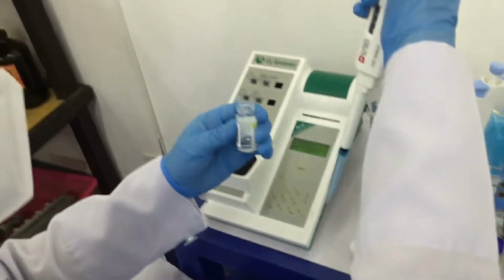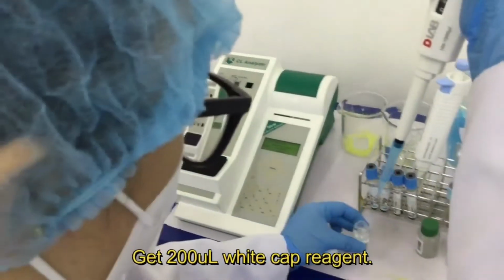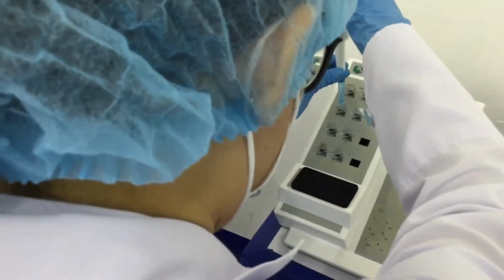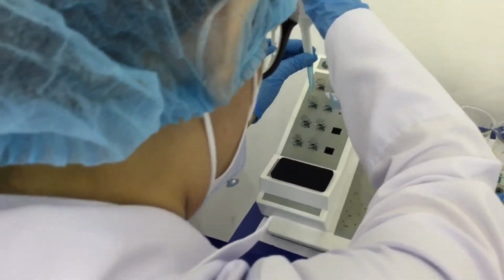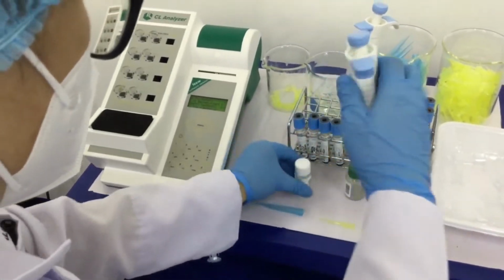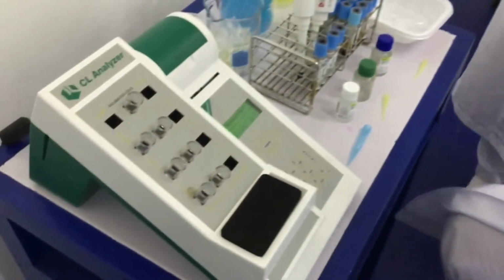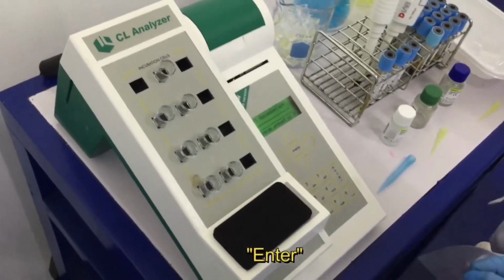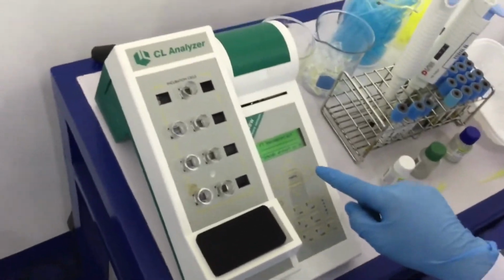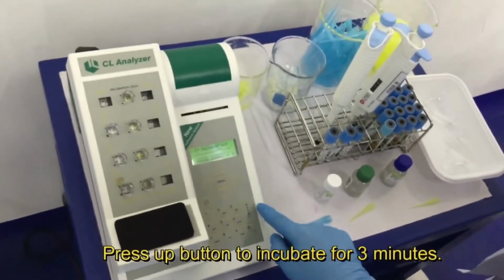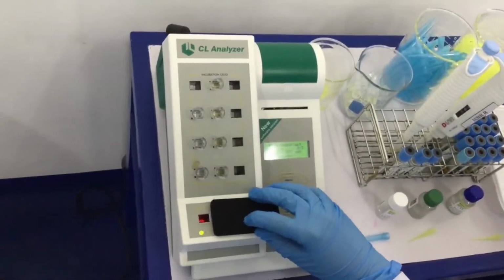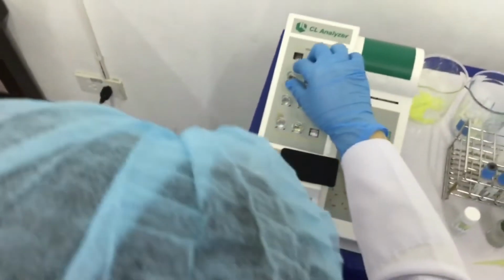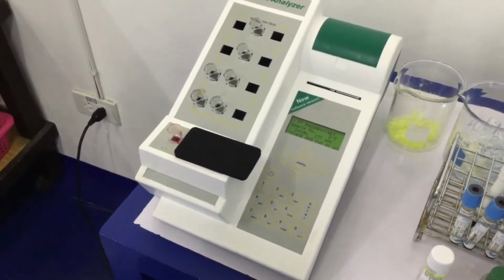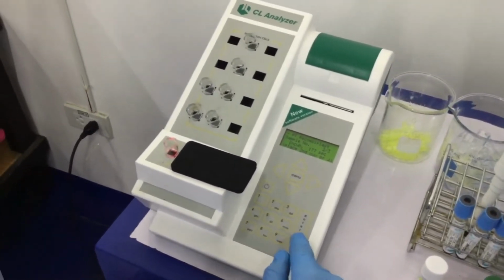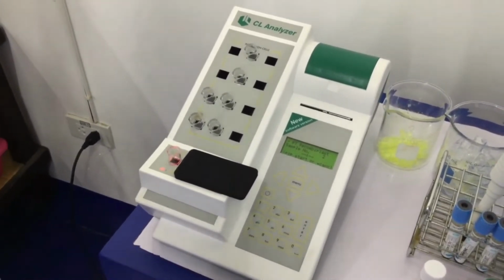In performing prothrombin time, add 200 microliters of the white-capped reagent to the cuvette. Then click Enter. Press the arrow up button to incubate for 3 minutes. Now transfer the cuvette and place it on the reading cell. Click Enter and add 100 microliters of the plasma to the cuvette.